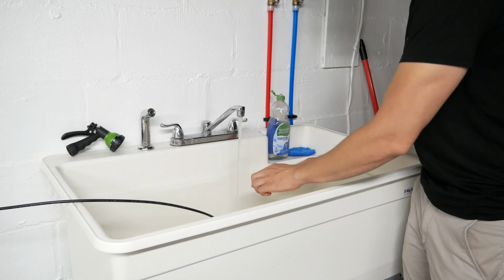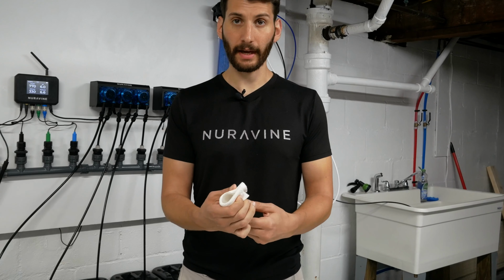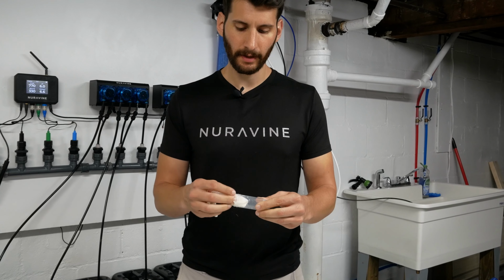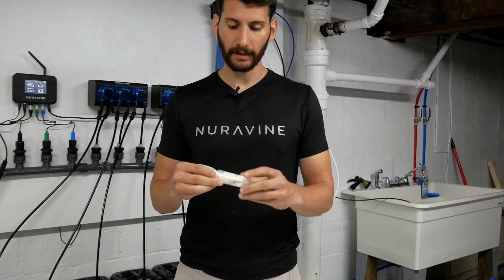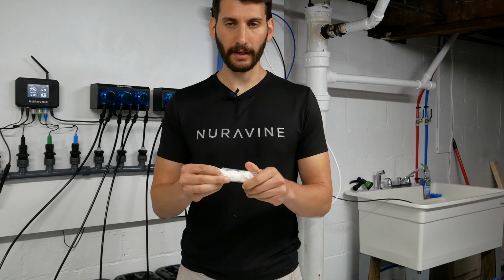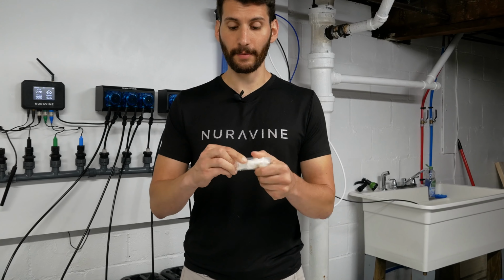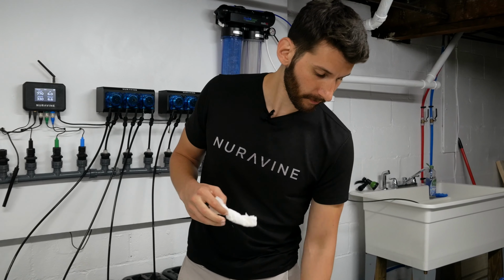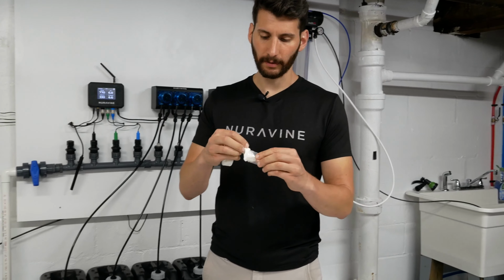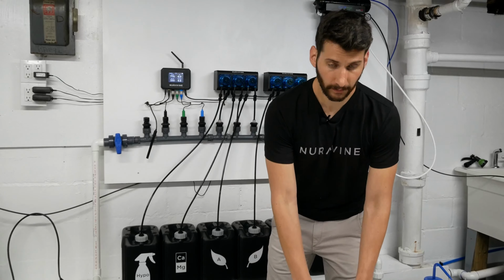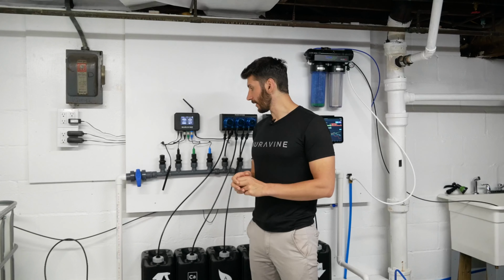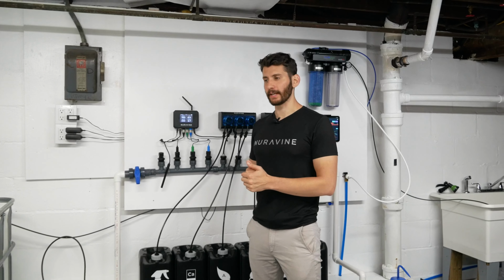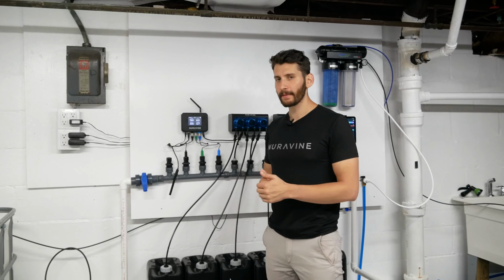So now I'm going to really wipe these things down, down the outside, wipe down the inside. We want them to really be clean, basically just like new, because we don't want the solutions to be contaminated at all. So I'm going to clean this one out. And we're done. So now that we've calibrated the EC probe, the next step is to calibrate the pH probe.